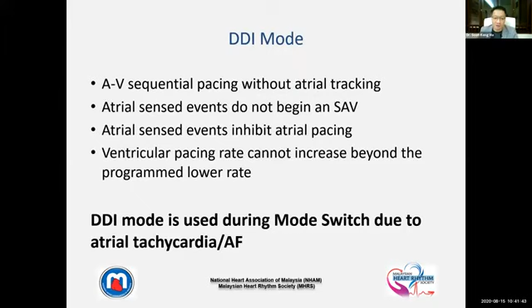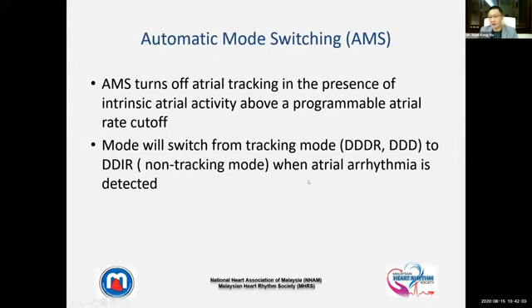Which brings me to this mode, the DDI mode, which is a non-tracking mode, the mode that we switch to for the patient if the patient has a very fast atrial rate in the beginning of the implant. And you may think that we need to keep readjusting the mode of pacing for the patient. In fact, no need. Nowadays, with modern pacemakers, they all have automatic mode switch, which will do the job for you most of the time. It switches in and out of pacing modes from DDD to DDI non-tracking mode for you.